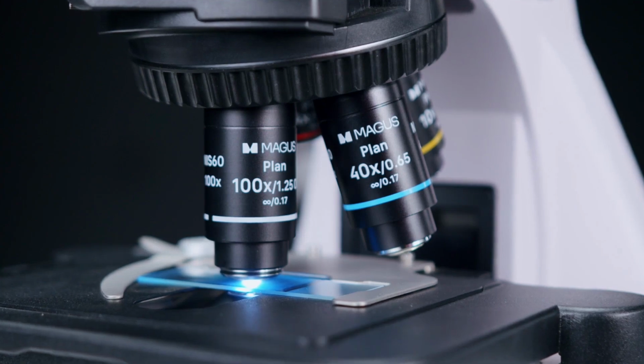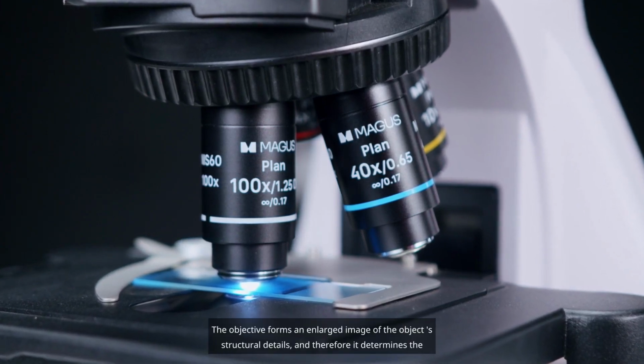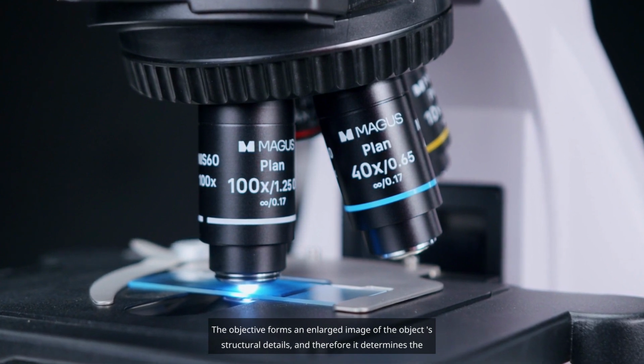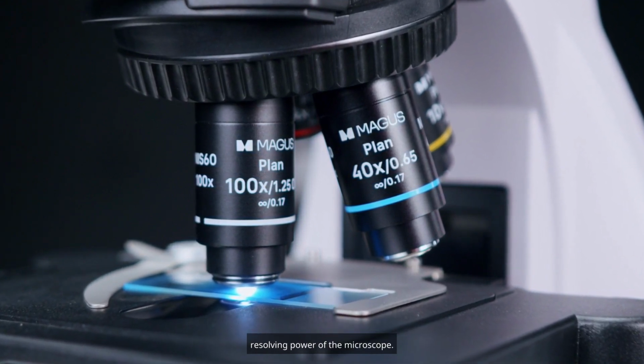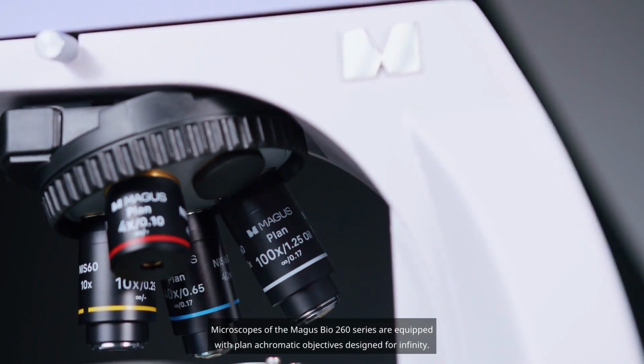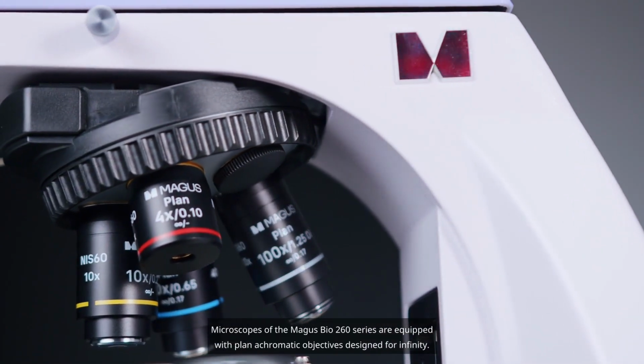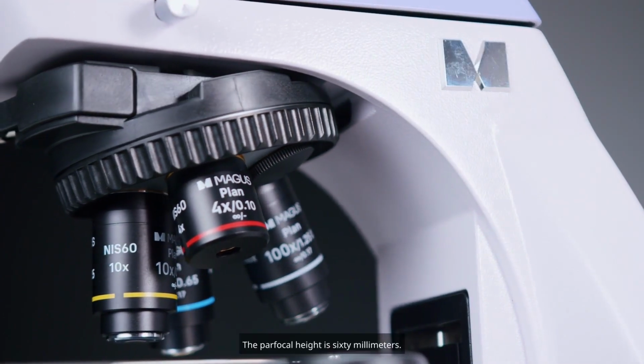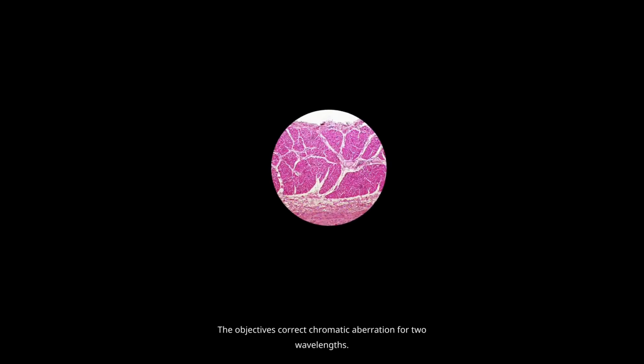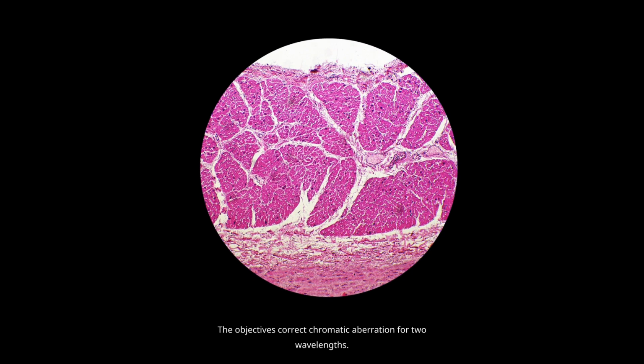The only component that interacts with the research object is the objective. The objective forms an enlarged image of the object's structural details, and therefore, it determines the resolving power of the microscope. Microscopes of the MAGUS Bio 260 series are equipped with planachromatic objectives designed for infinity. The parfocal height is 60 millimeters. The objectives correct chromatic aberration for 2 wavelengths. The contours of the object are clearly delineated, color rendition is not distorted, and the plan correction rectifies image curvature across the field of view. Such objectives are standard for clinical diagnostic laboratories.